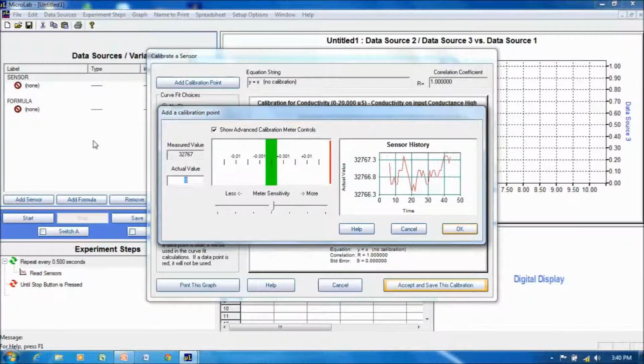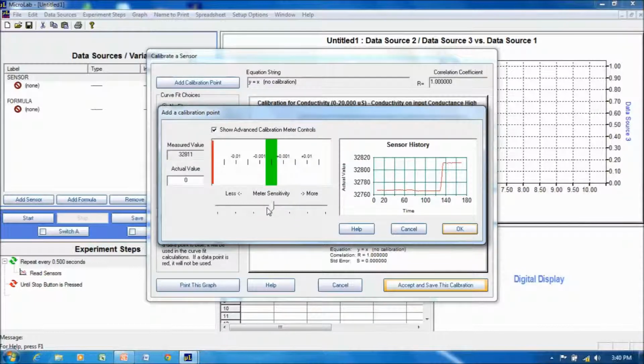So we'll remove the sensor from the deionized water. I'm going to wipe it off with a clean tissue. And then I'm going to use the 45 microsiemens per centimeter sample. Lower it in. Check for bubbles. There are none. And we'll just wait for that to stabilize. We'll type in the actual value of 45 microsiemens per centimeter. That looks pretty good.